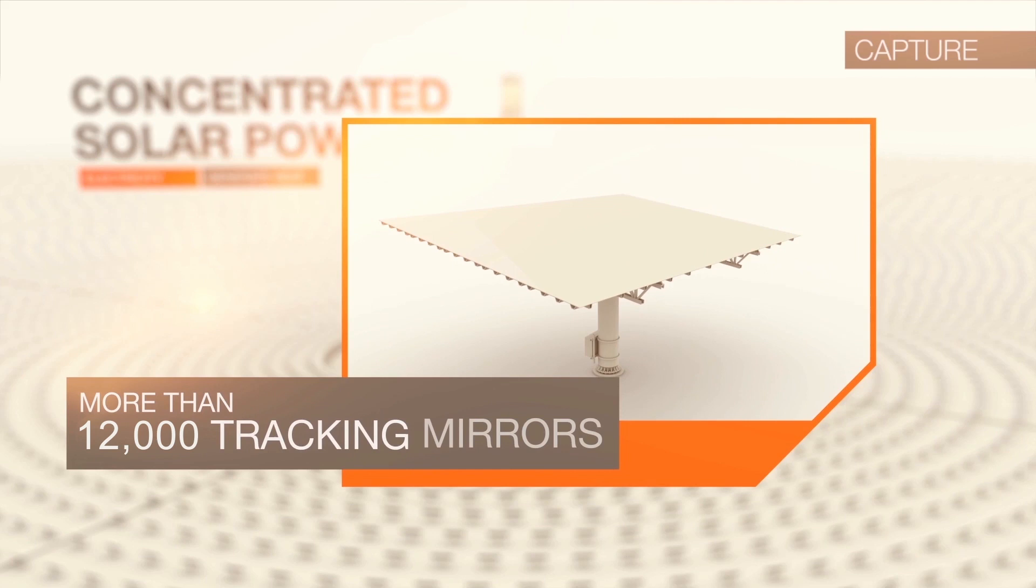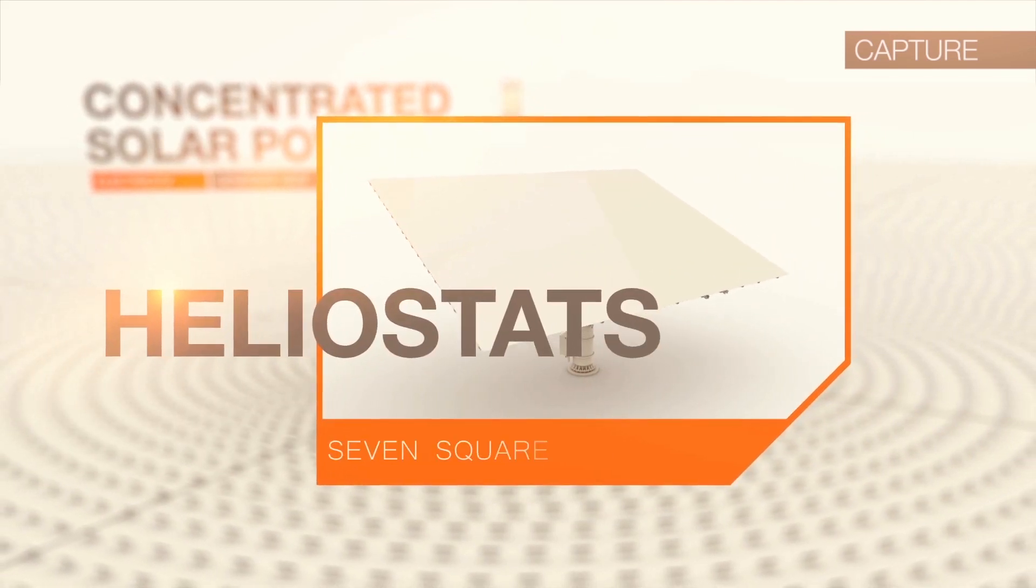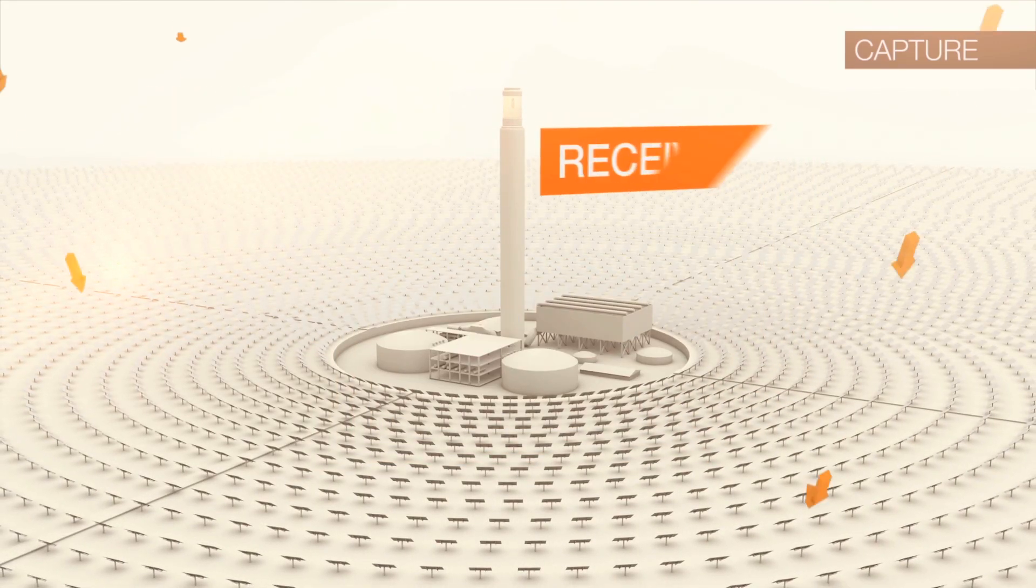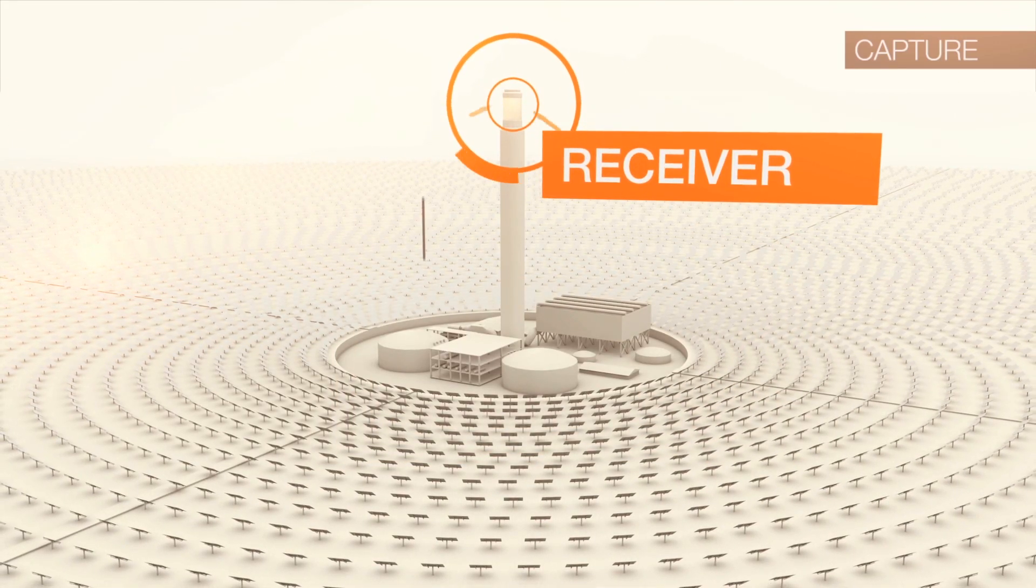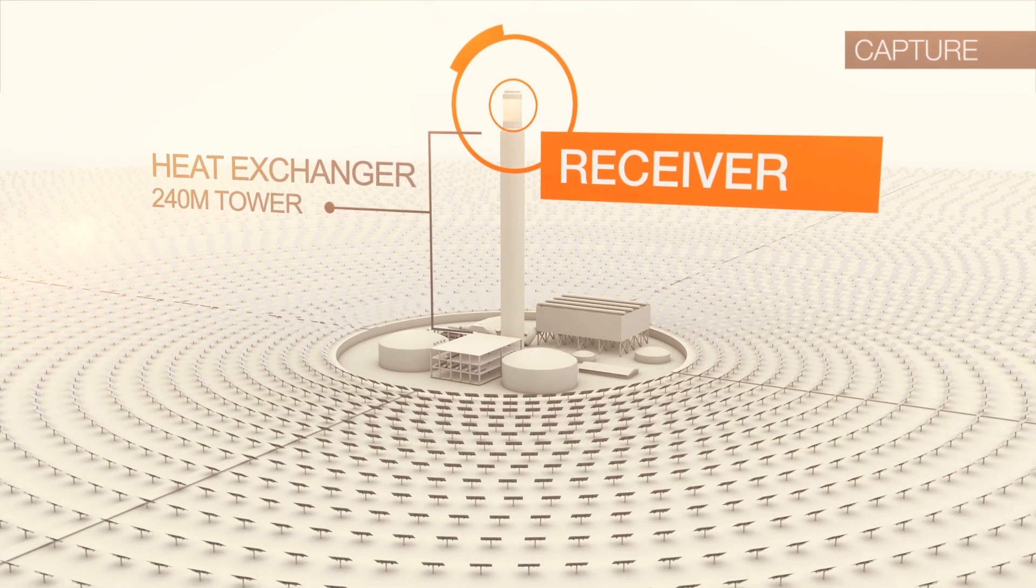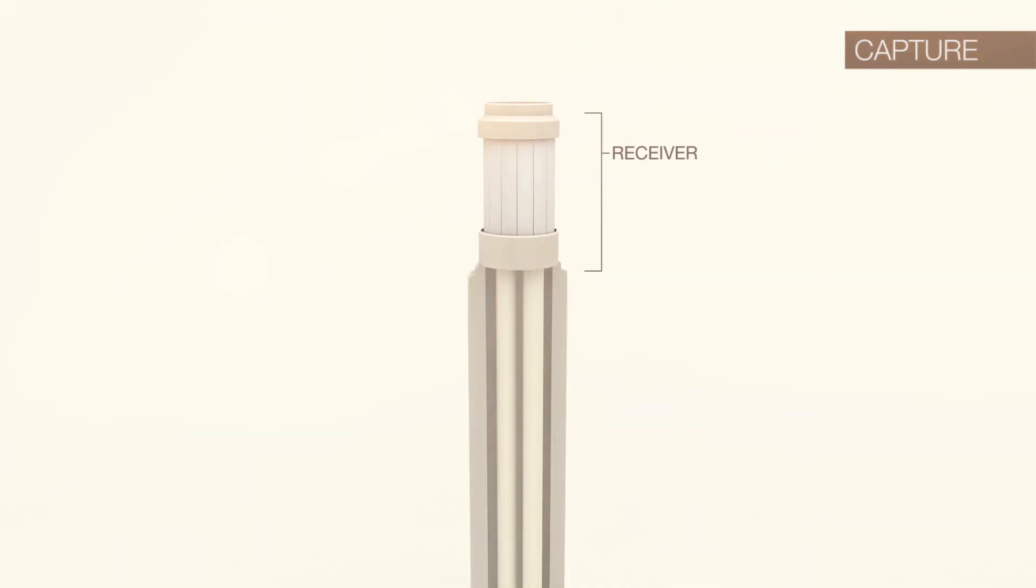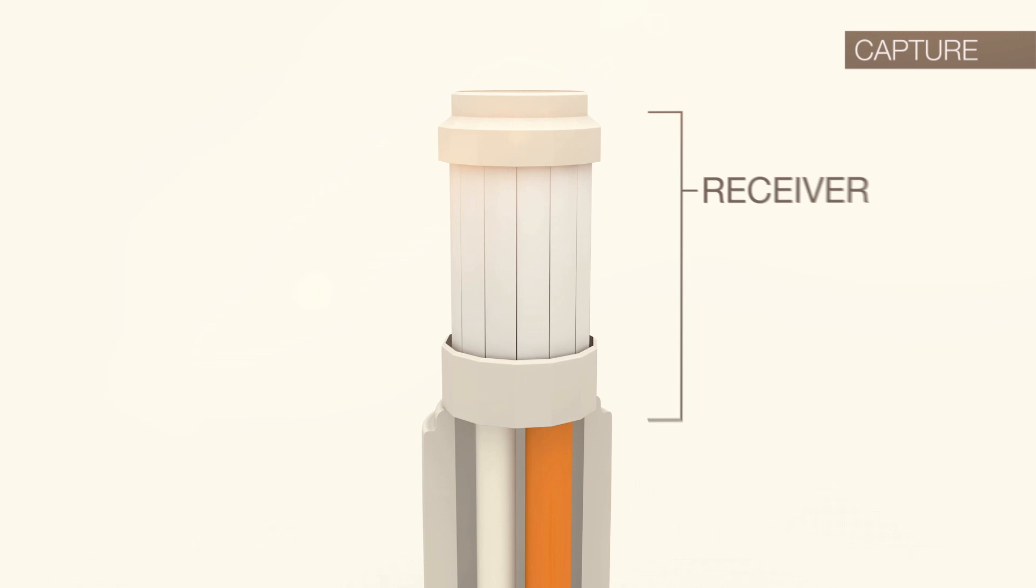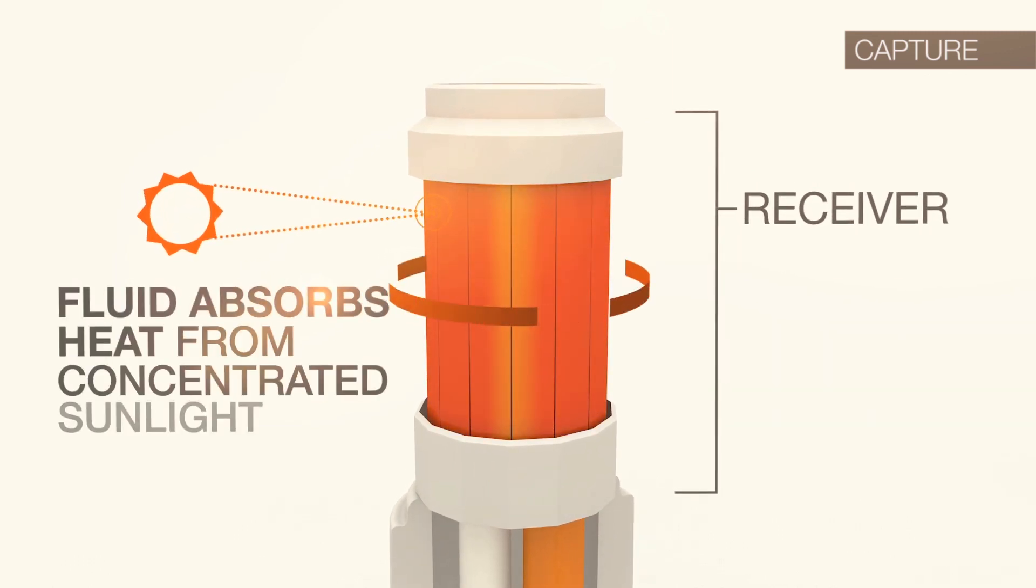More than 12,000 tracking mirrors, called heliostats, reside in a 7 square kilometer field where they reflect and concentrate sunlight onto a large heat exchanger called a receiver that sits atop a 240 meter tower. Within the receiver, fluid flows through the piping that forms the external walls. This fluid absorbs the heat from the concentrated sunlight.